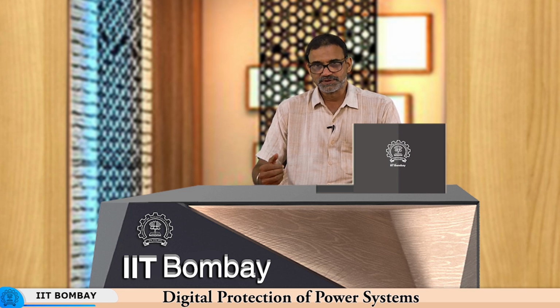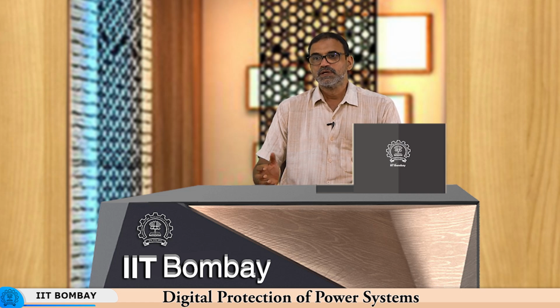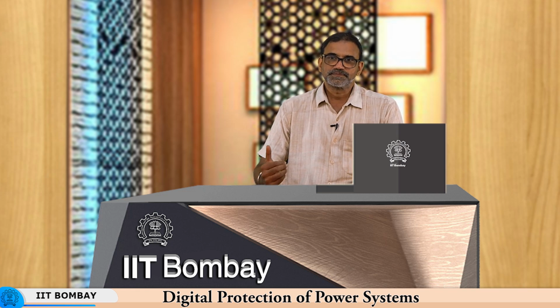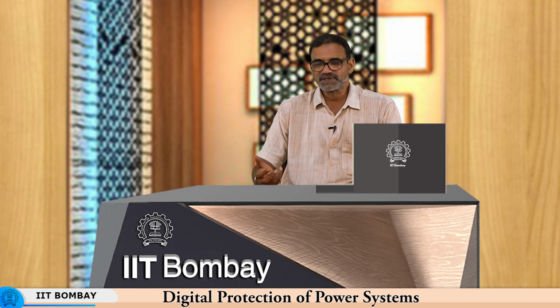The relay can utilize that information also. For example, in a traditional current differential scheme, if you did not have voltage information, and you're doing current differential protection of a transformer, then if there is an inrush current, you will have to have some way of restraining for that, like second harmonic restraint. But now, if you know the flux present in the transformer, measured using a PT, and that information is made available to the numerical relay, you can design a better scheme for inhibiting relay tripping on inrush currents.